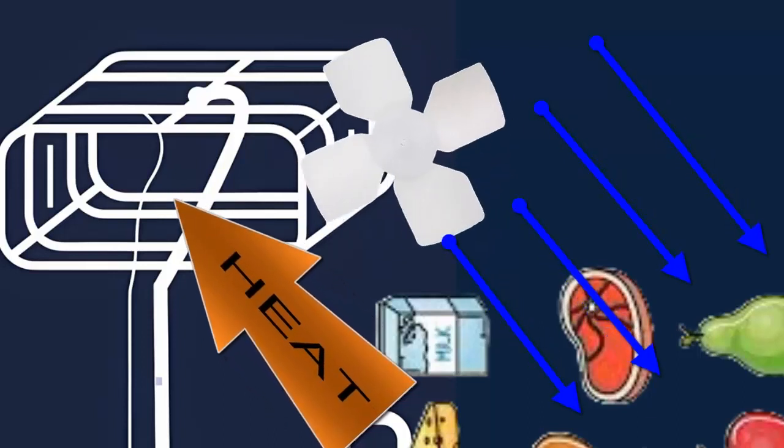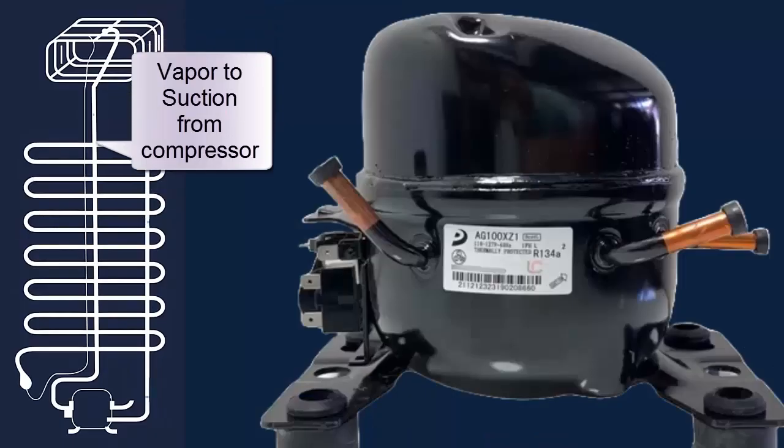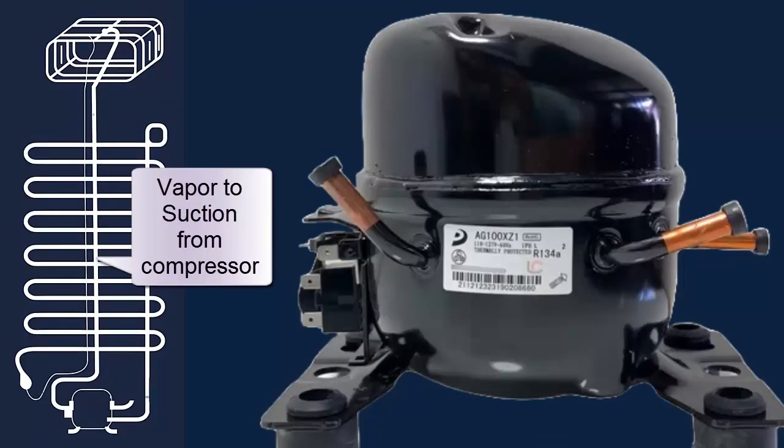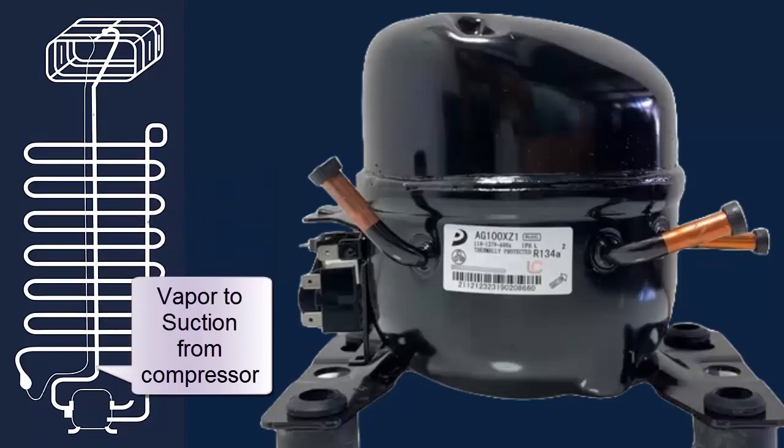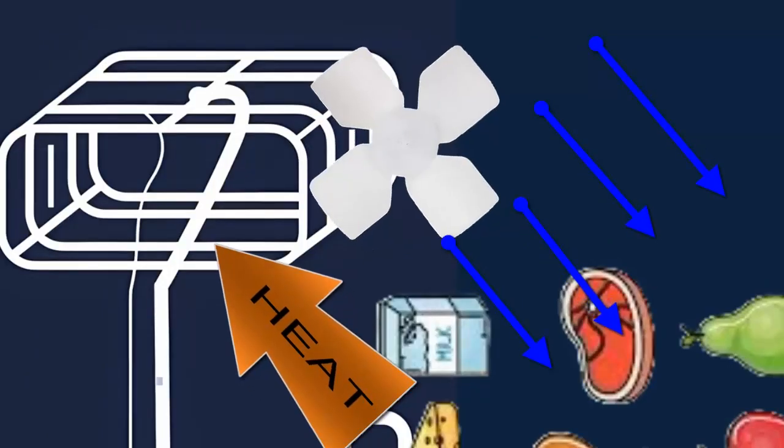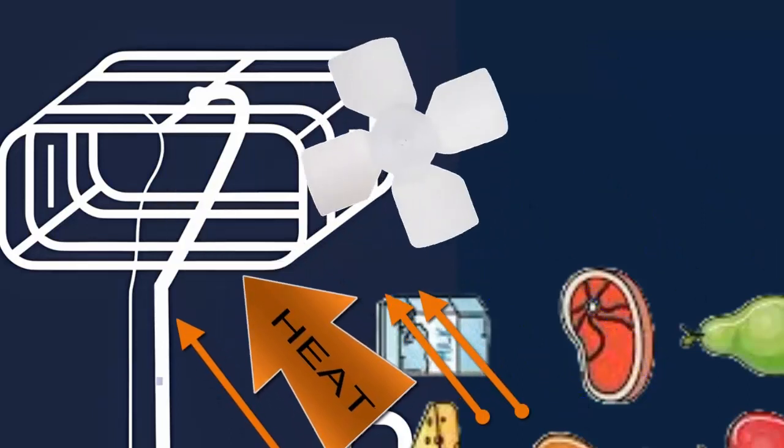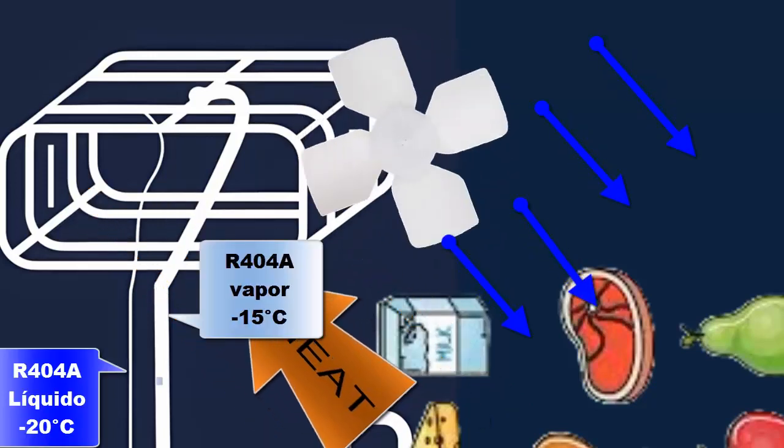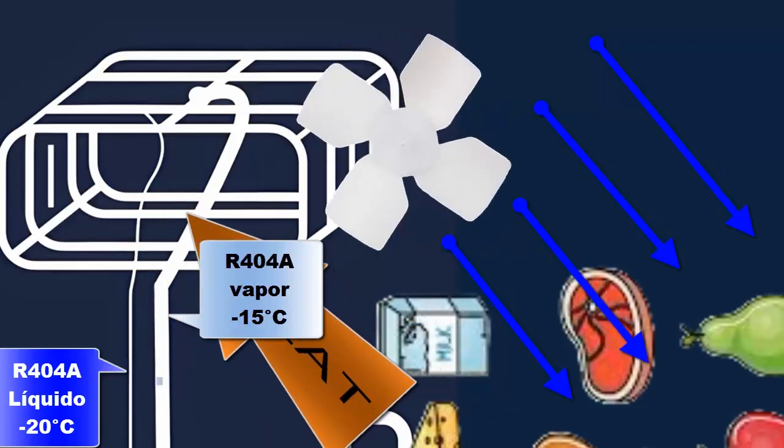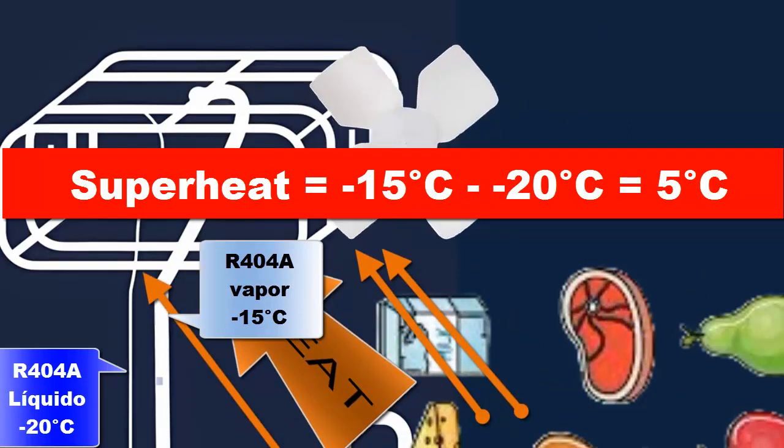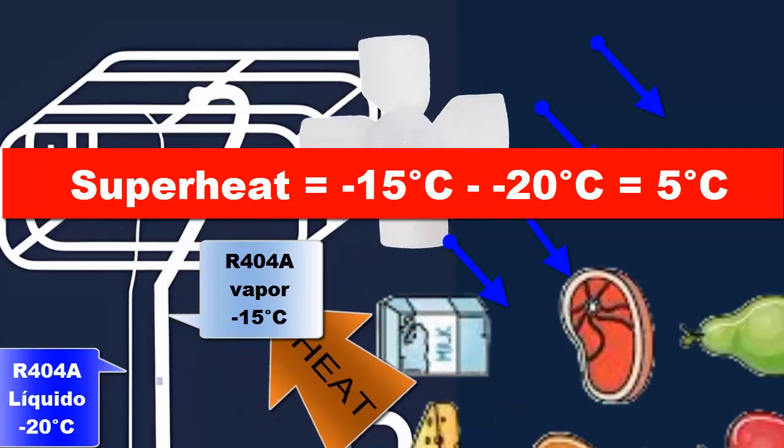The R404A, now in a gaseous state, and with a slight temperature increase called superheat, is suctioned by the compressor. For this case, let's assume that the temperature of the R404A refrigerant in a gaseous state is minus 15 degrees Celsius. This means that the R404A refrigerant goes from minus 20 degrees Celsius to minus 15 degrees Celsius, so in this equipment, the superheat is 5 degrees Celsius.